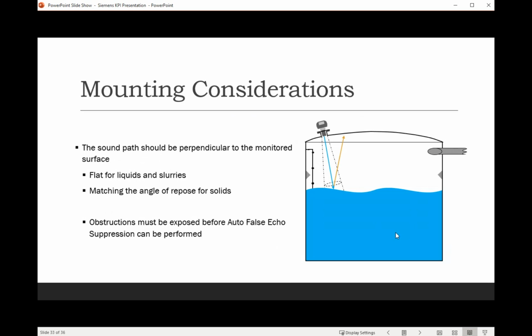Another thing to keep in mind for a stilling well, you want to have a little vent on there to keep the pressures equalized. You don't want it to get too pressurized and then throw off your reading in the stilling well. Also, on the transducer with the coupling, when you're mounting it with that 1-inch MPT, you want it to be hand tight. You don't want it too tight, or it would cause excessive ringing and probably give you lower signal strength coming back to the transducer itself. Also, just keep in mind with all ultrasonics that there is about a 1 foot blanking distance from the transducer face down a little bit. So within 1 foot of the transducer face, this transducer can't see anything.